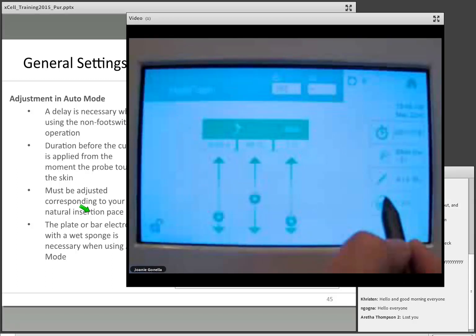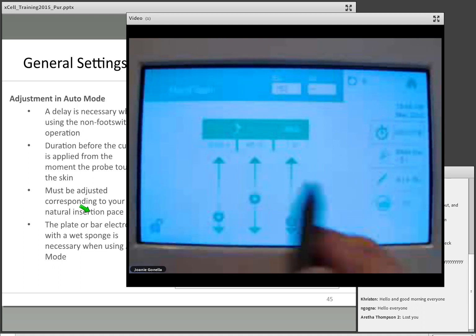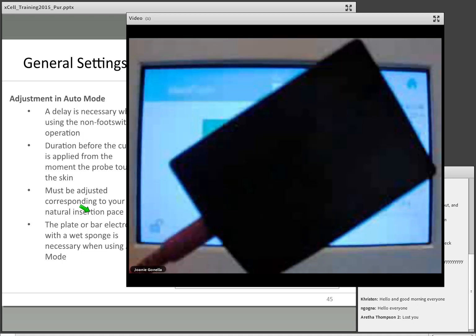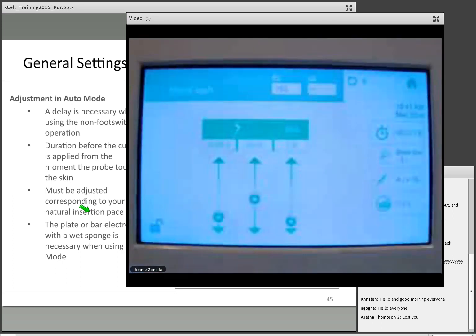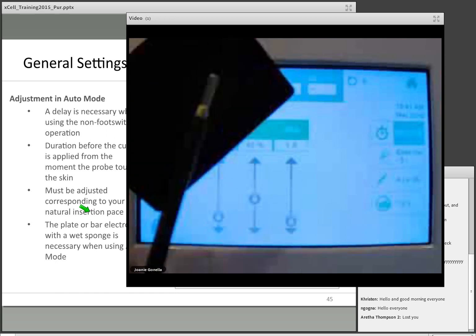When I'm on auto mode, this changes. Now I have the pedal in a circle with a line through it, and this says 1 second, which is my activation delay. I give my client the ground covered with the paper towel that is wet or the sponge, and when I make contact with the skin, it will automatically make a little tink noise. Make sure you lock your padlock. And then I think this is the right probe. Let me see if it's going to do it. So all I'm doing is I'm doing the connection here on the probe cord. But you can hear that noise.